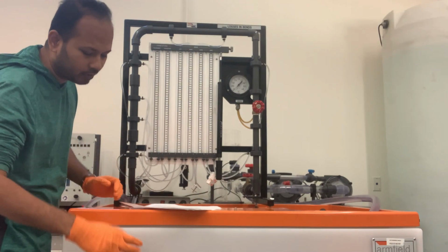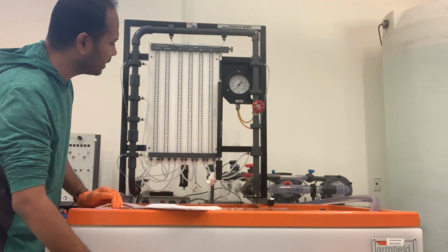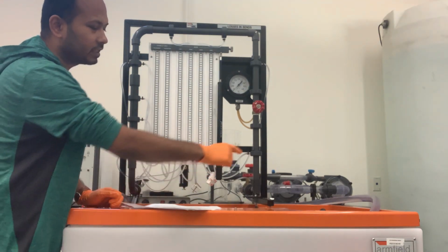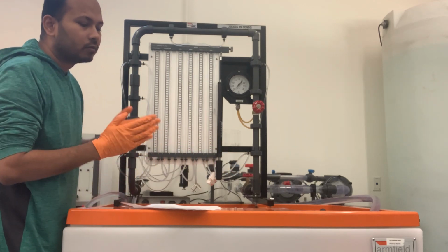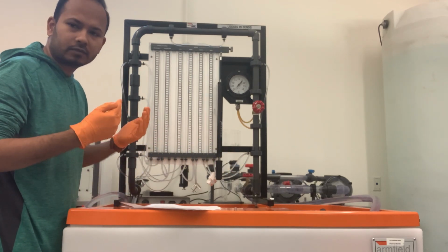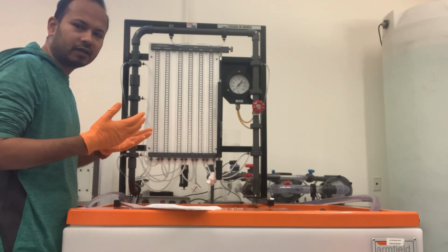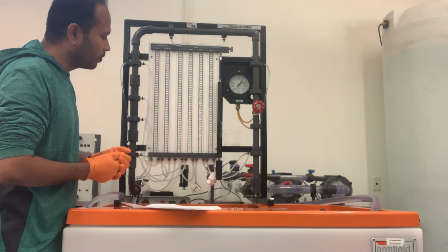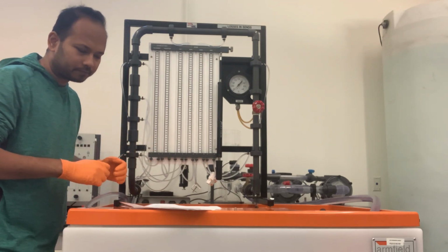So how do we do that? We're going to keep reducing the flow rate through the bench valve gate, and we're going to measure the water collection over there, and from there, given the time, what is the volume of the water? If we can divide that, we can find the flow rate, and from there we can measure whether it is below 17 or not.